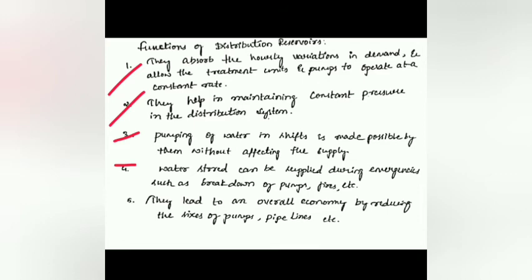Fourth point, stored water can be supplied during emergencies such as breakdown of pumps and fires. Even if pumps are not working, we can manage a few days with the stored water in the reservoir. And last point, they lead to an overall economy by reducing the sizes of the pumps and the pipelines. Since constant head is available, it can supply the water even in both systems of supply. So because of that, large pump and pipeline sizes are not required. If only pumping is maintained, pumps of high capacity should be purchased in order to meet the requirement of the public. So these are the functions of the distribution reservoir.